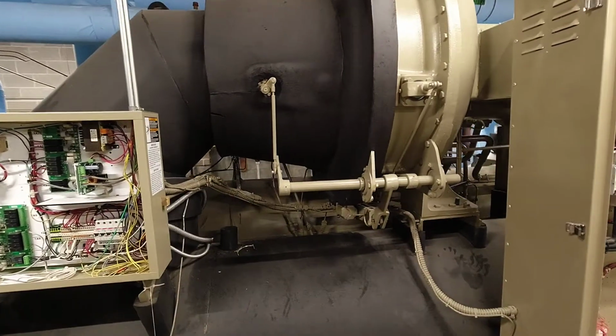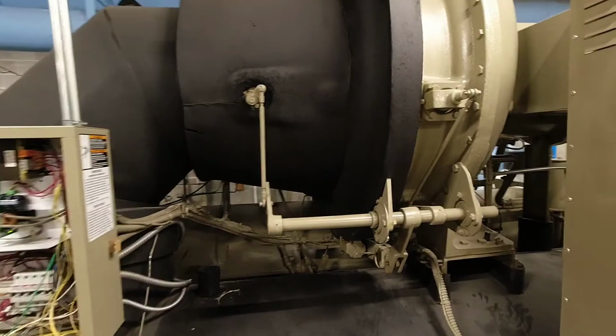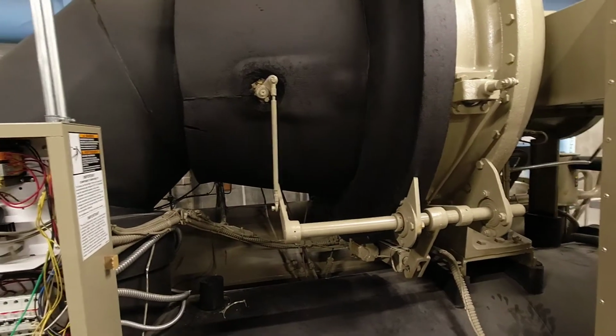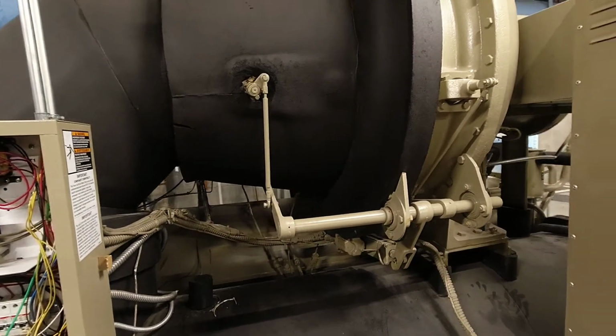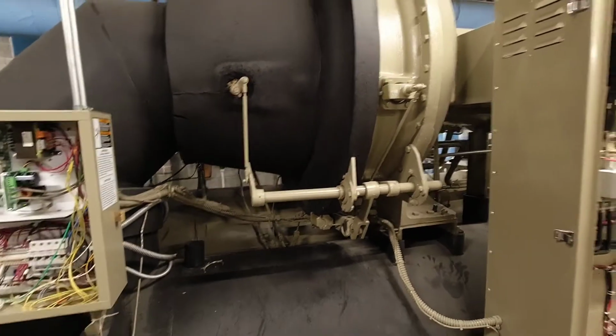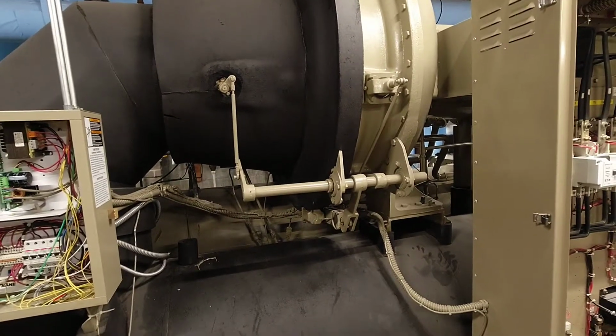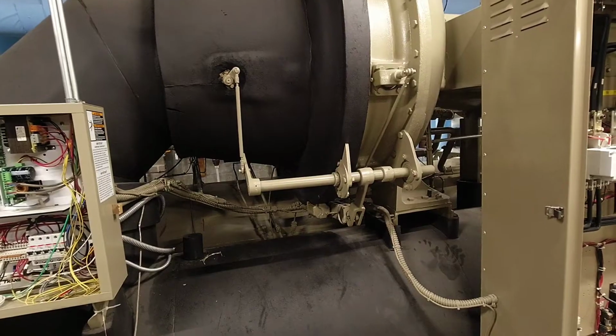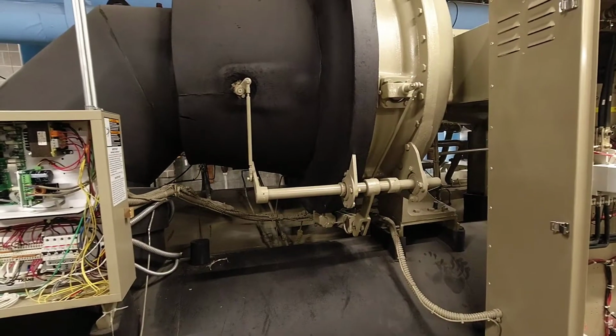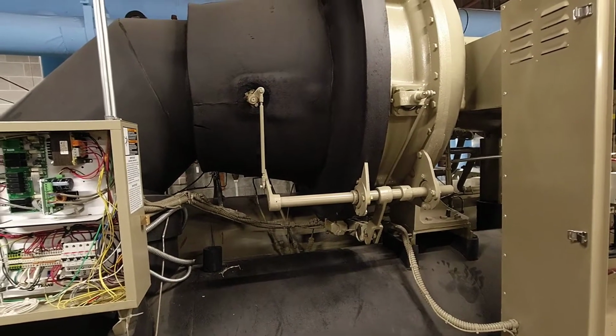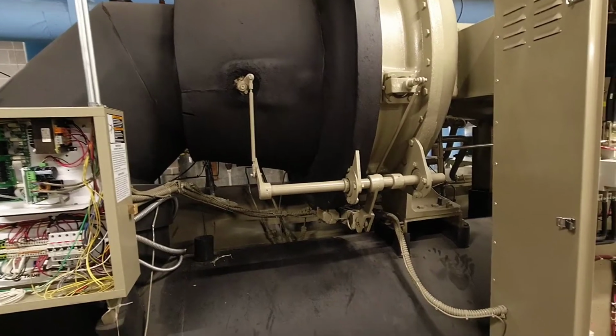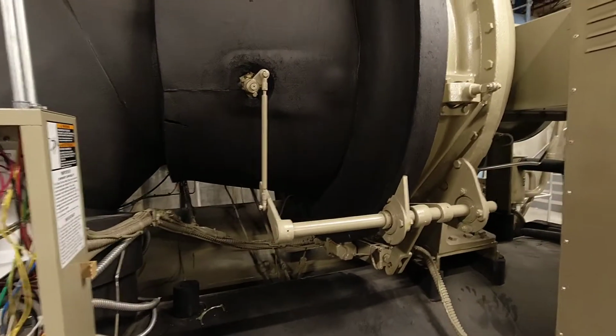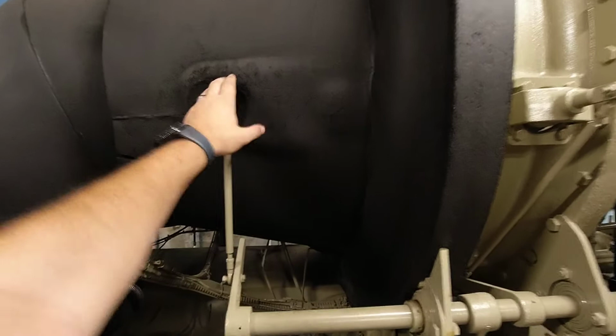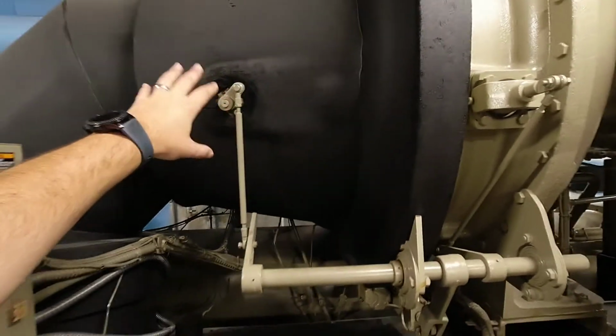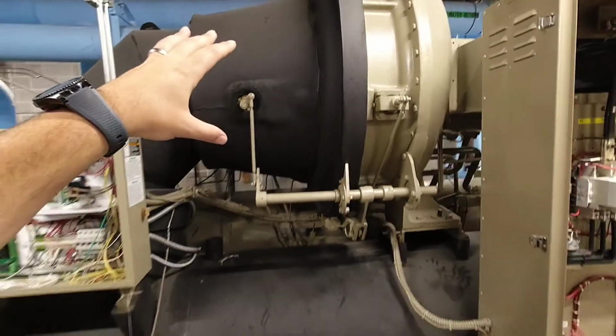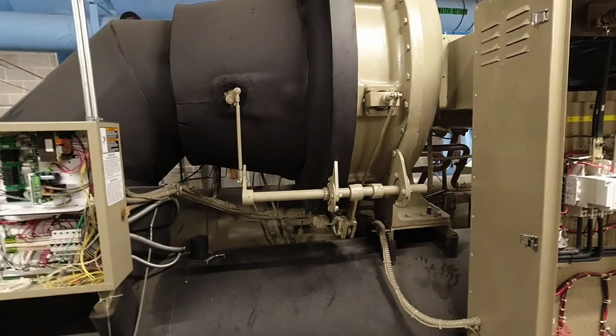You want this chiller to stay online as much as possible. So just keep that in mind, as we don't intentionally want to set it up or put parameters in place where it's constantly turning off and on. It's a lot of extra stress for the chiller, and you lose a ton of efficiency in that process. Anyway, guide vanes allow very strong loading and unloading control.